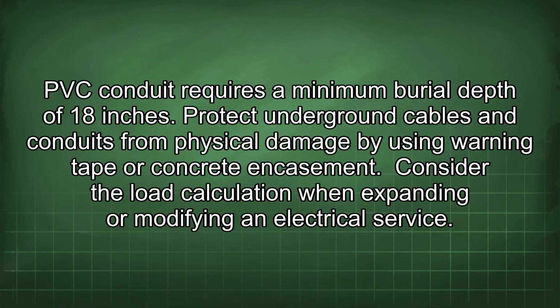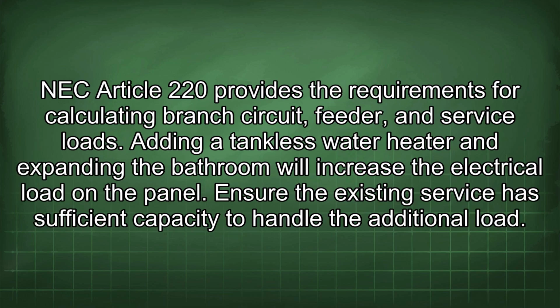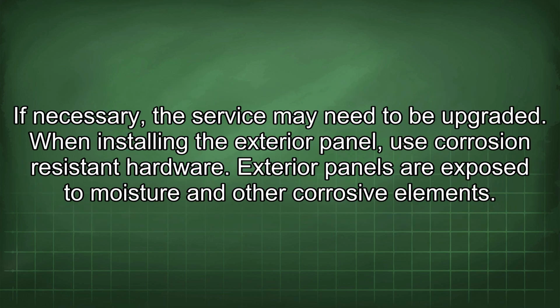Consider the load calculation when expanding or modifying an electrical service. NEC Article 220 provides the requirements for calculating branch circuit, feeder, and service loads. Adding a tankless water heater and expanding the bathroom will increase the electrical load on the panel. Ensure the existing service has sufficient capacity to handle the additional load. If necessary, the service may need to be upgraded.